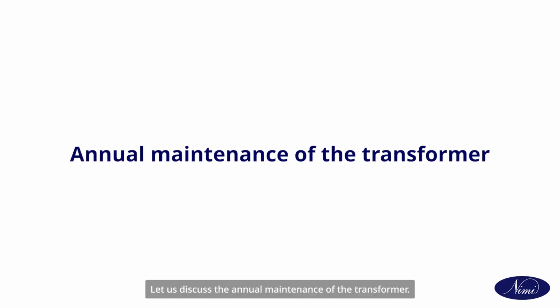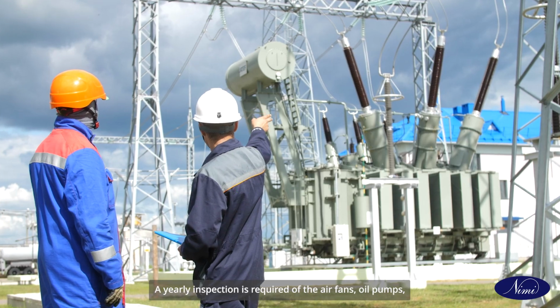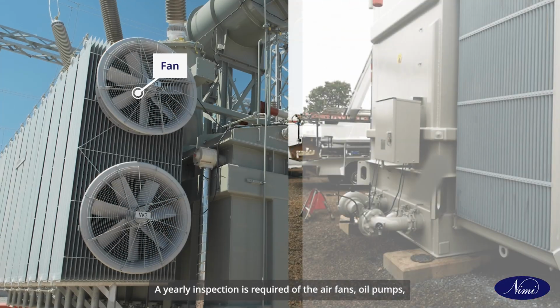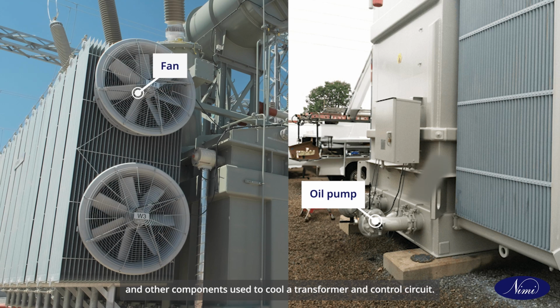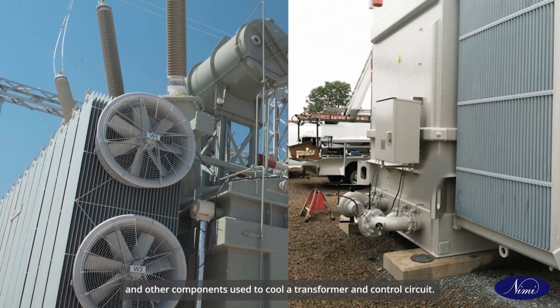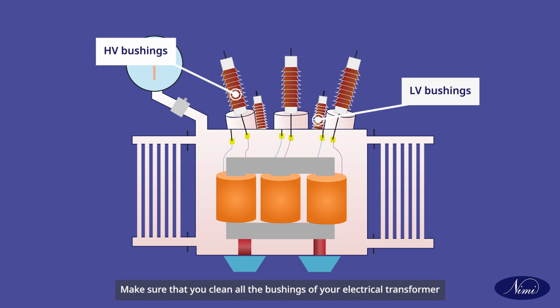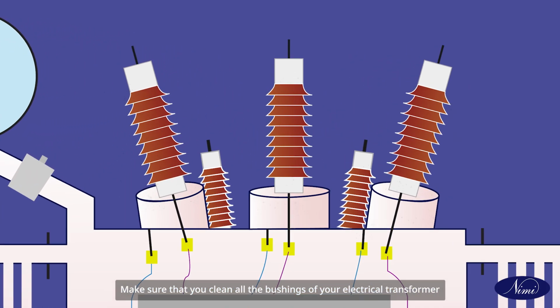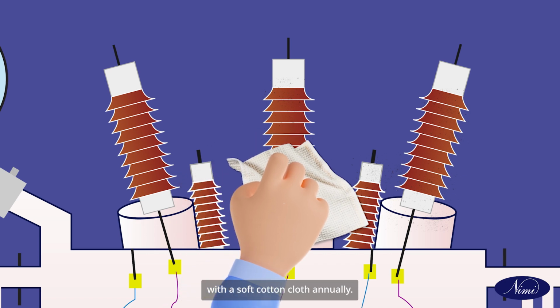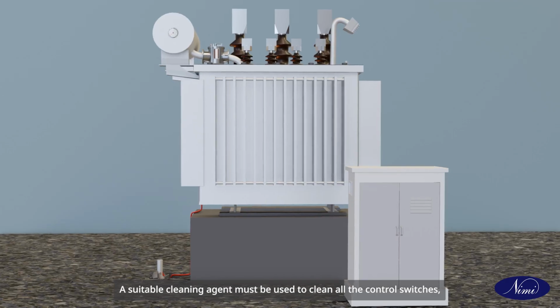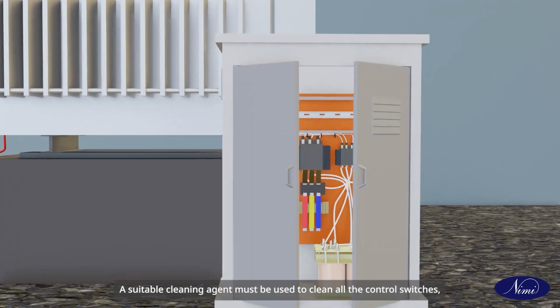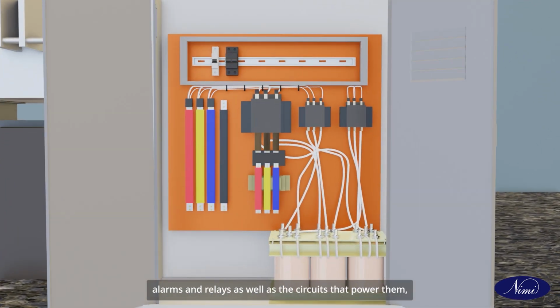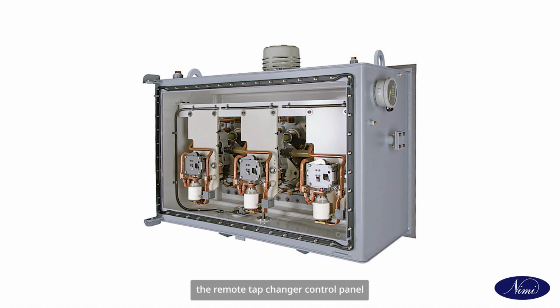Let us discuss the annual maintenance of the transformer. A yearly inspection is required of the air fans, oil pumps, and other components used to cool a transformer and control circuit. Make sure that you clean all the bushings of your electrical transformer with a soft cotton cloth annually. A suitable cleaning agent must be used to clean all the control switches, alarms, and relays, as well as the circuits that power them, the remote tap changer control panel, and relay and control panel.